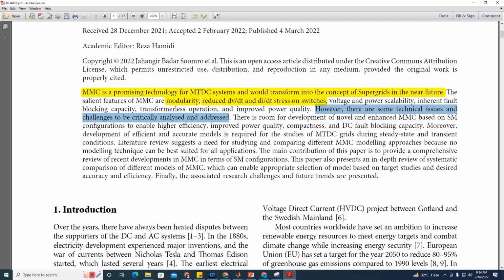Literature reviews suggest a need for studying and comparing different MMC modeling approaches, because no modeling technique can be best suited for all applications. Suppose you want to analyze internal submodule fault of MMC, checking for flashover problems or damage to the internal submodule capacitor - if your focus is internal submodule, detailed switch modeling or type 1 can be preferred and used for the studies.